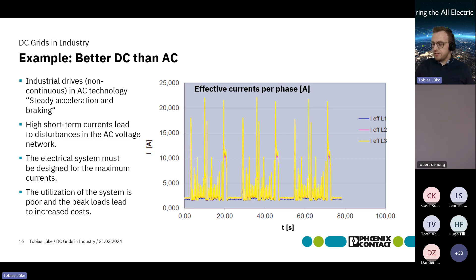Even if these current peaks only occur several times and are not constant, compare that to a DC grid: it allows feeding back the potential energy by lowering the load again into the DC grid, making it available for other loads that are lifting. You get the acceleration power and the braking power balancing out, so the overall effect on the upstream grid is less, the grid design is smaller, and the use of recuperation energy was the main motivation for the research project DC Industry.